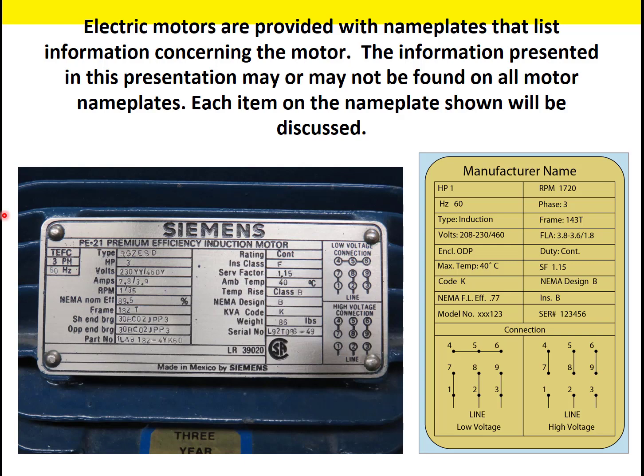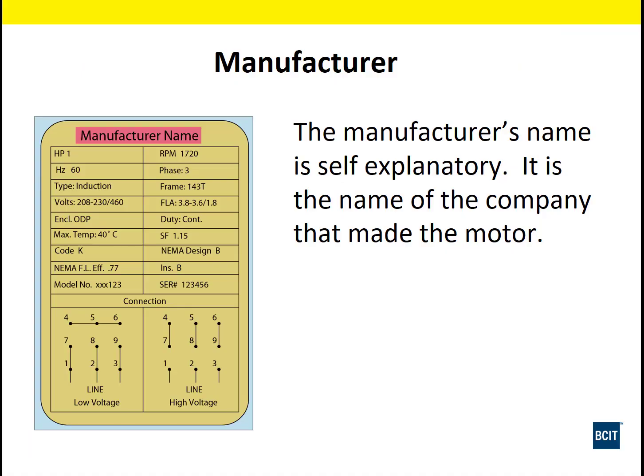On the left here we have a Siemens nameplate, slightly different than the sample we're going to look at on the right, where we have enclosure types, phase information, voltage and all these things. We're going to have a look at that. First thing, obviously, manufacturer's name. Who made the motor? Name of the company. On the previous slide, that was Siemens.